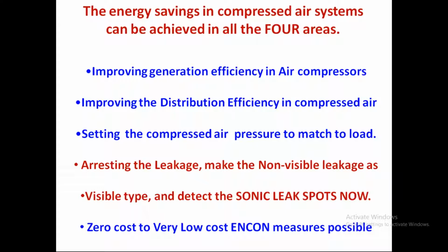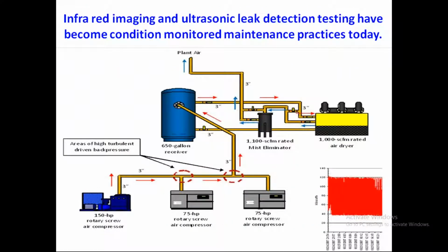You may have an excellent generation compressor which gives almost 0.15 kilowatt per CFM, but still, if you are leaking through the pipes and through the equipment, it is a big loss to the industry. It is a silent loss to the industry. Coming to the piping, where you find the T connection piping, there is turbulence. Normally, the velocity to be maintained is around 6 to 10 meters per second in the compressed air header.